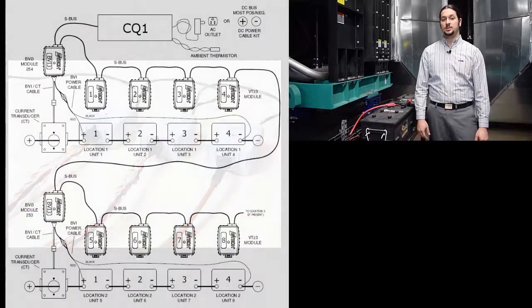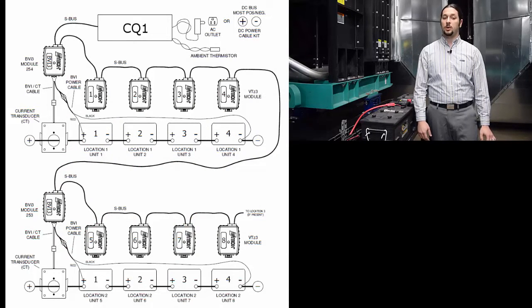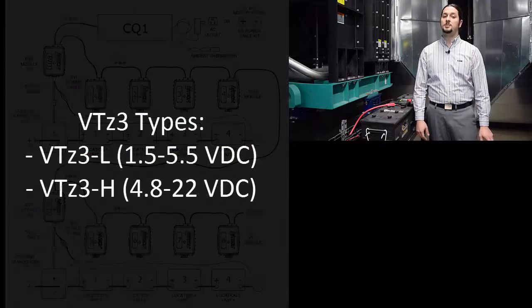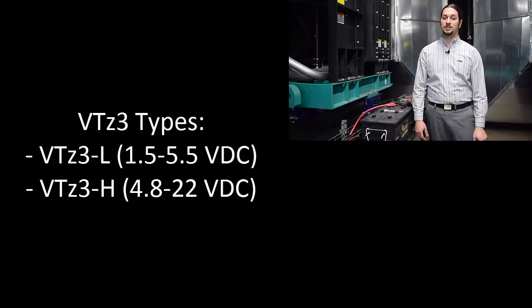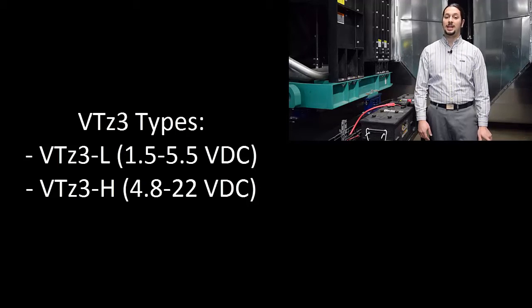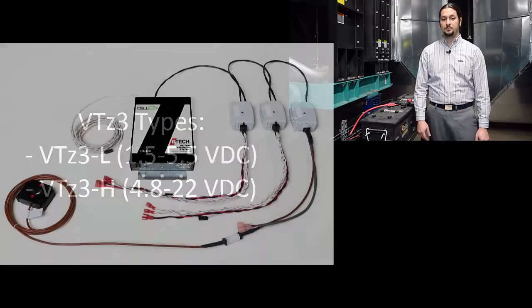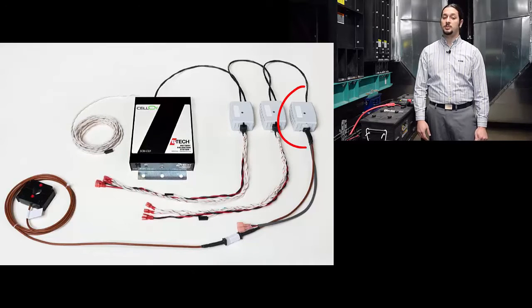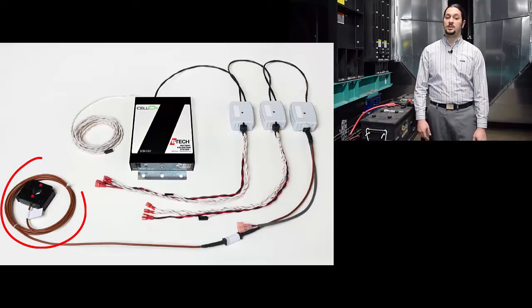Each one of these modules connects to a single battery using a wiring harness that attaches to the battery using tab washers. There are two types of VTZ3, VTZ3-H and VTZ3-L. The VTZ3-L is compatible with batteries having nominal voltage of 1.5 to 5.5 volts DC. The VTZ3-H is compatible with batteries having nominal voltage of 4.8 to 22 volts DC. Another optional module is the BVI-3 module, the component that measures string current and string voltage. Each one of these modules has a matched current transducer.